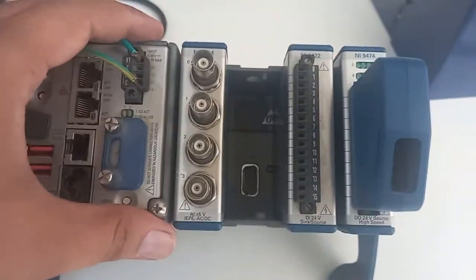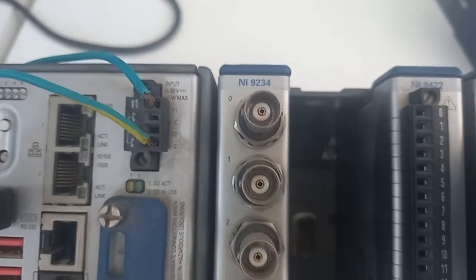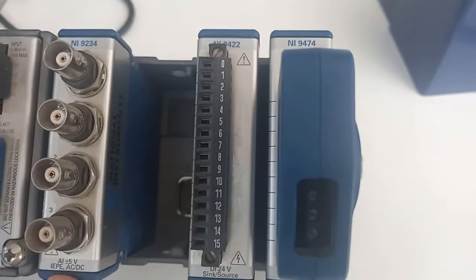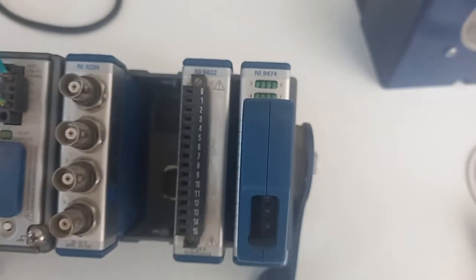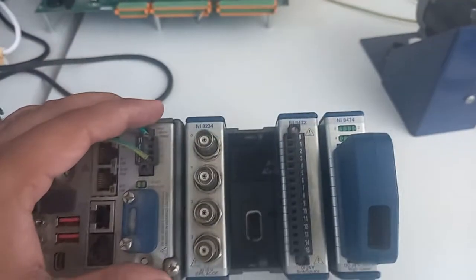It has four input/output modules. We have different types of NI modules — it can be an analog input module, analog output module, digital input module, and digital output module. You can see here: this is NI 9234, an analog input module at plus/minus 5 volts. This is NI 9422, a digital input at 24 volt sink/source. This is NI 9474, a digital output module at 24 volt source high speed.